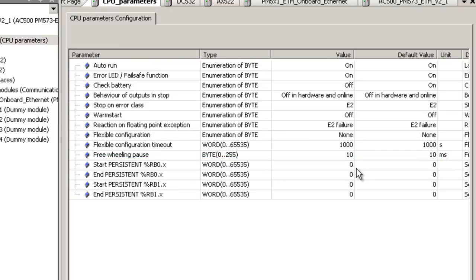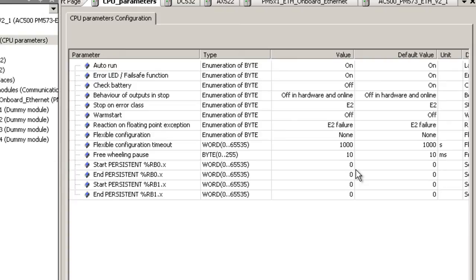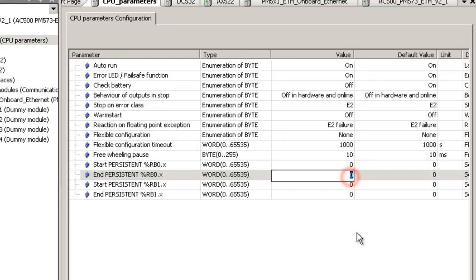In the row start persistent percent RB0.x, the first address remains zero which means the start address of the buffered area is percent RB 0.0. In the next line, End PERSISTENT %RB0.x, we fill 9 because 10 bytes fill the same area as five words.